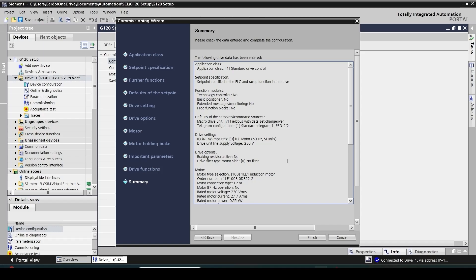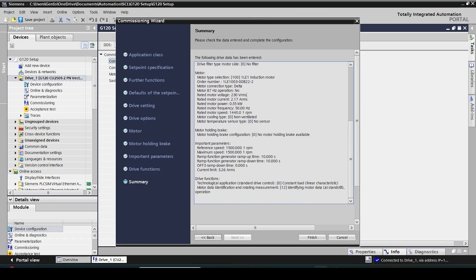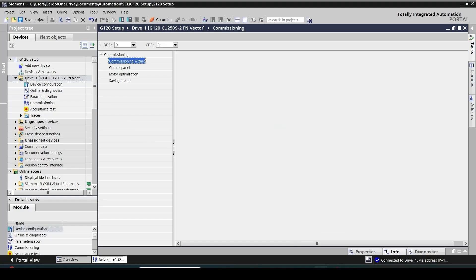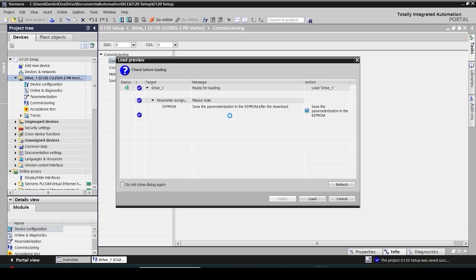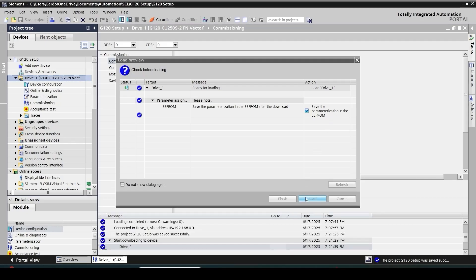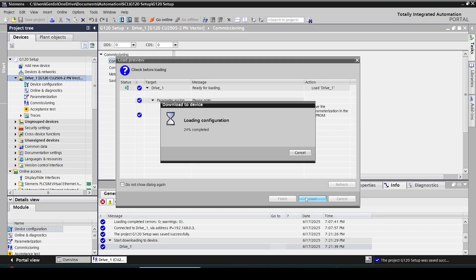Here is just a summary. You just need to verify everything is correct. If something is not correct you can simply go back and then update your configuration. I click finish here and then select my drive. I can save my project and then download the settings into my drive, and then I can pick save parameterization in the EEPROM of the drive as well. Configuration is fully loaded and depending on your drive type, you may hear the ticking sound of some relay coil energized or de-energized.